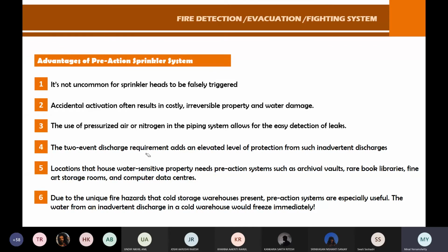The 2 event discharge requirements add an elevated level of protection from such inadvertent discharges. Locations that house water sensitive property need a pre-action system. Water sensitive activities are like archival vaults, imagine you are having a history library, and you have these old beautiful old books, and there is a fire there, or there is this kind of mistake there.